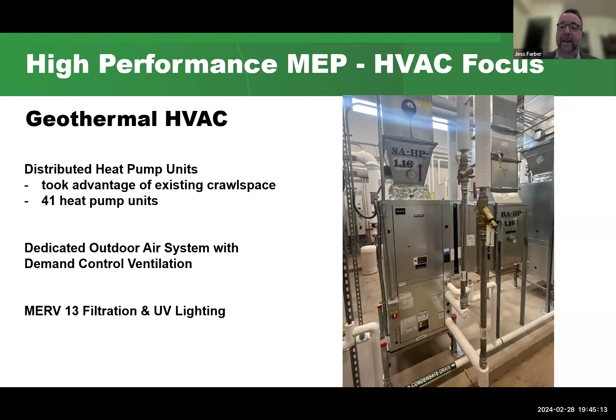We also have dedicated outside air systems to provide the ventilation air we want. During design we were able to improve it to address filtration issues that were emerging through post-pandemic planning, so we have the ability to put filters in the heat pumps themselves as well as in the fresh air systems.